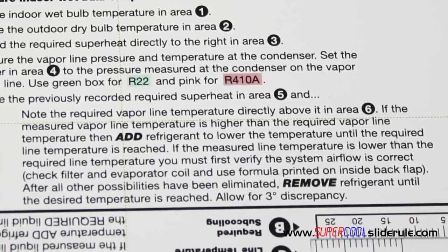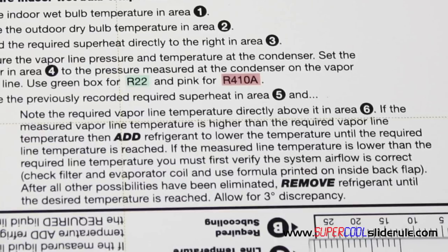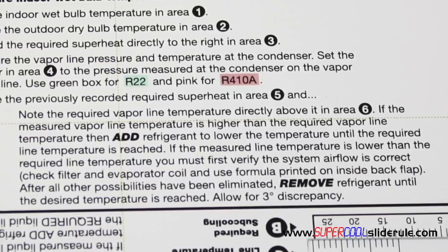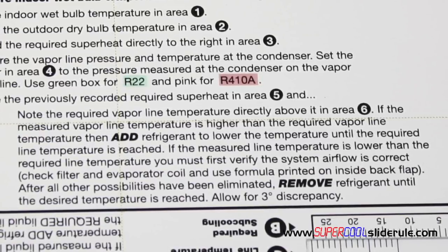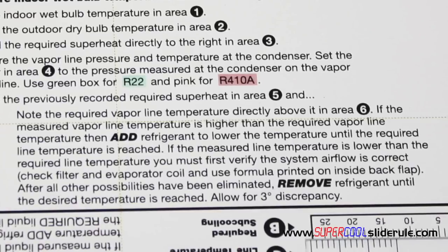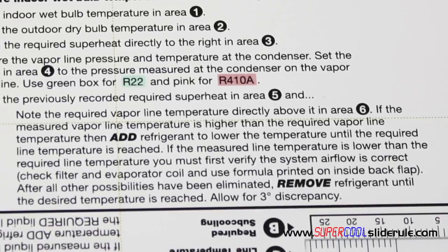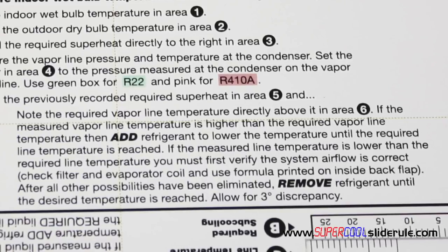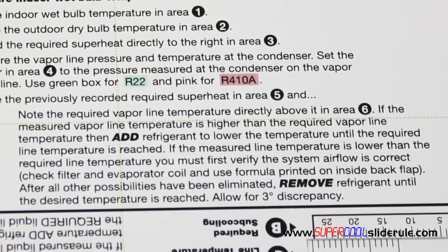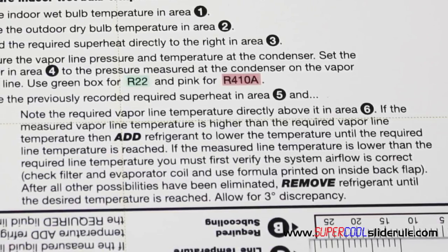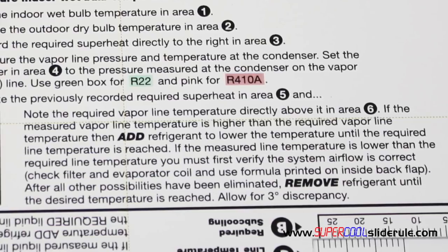And remember to be patient. Add a little refrigerant at a time and wait a minute or two, then add a little bit more. Now, if your temperature is lower than 50 degrees, you need to perform the test for correct system airflow and make any recommendations. After all of the possibilities have been eliminated and your measured line temperature is still below 50, the removal of refrigerant will be necessary.